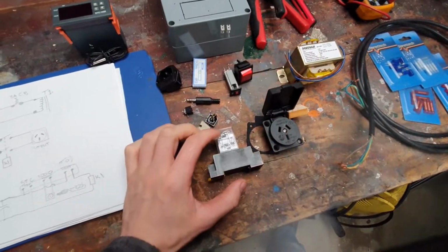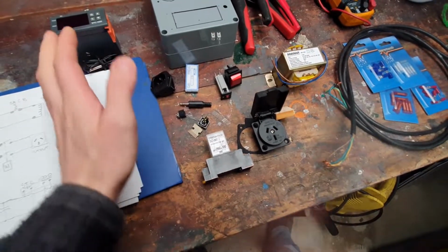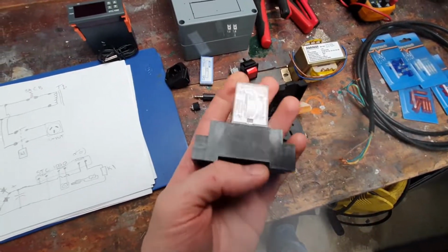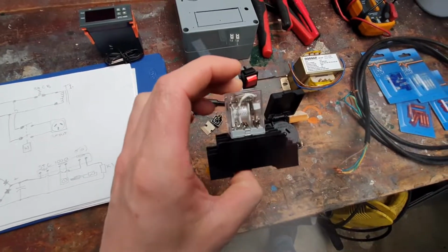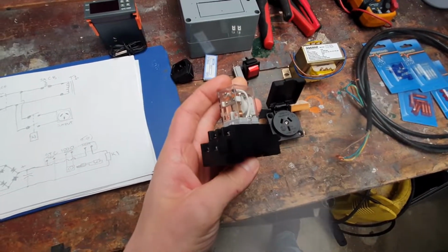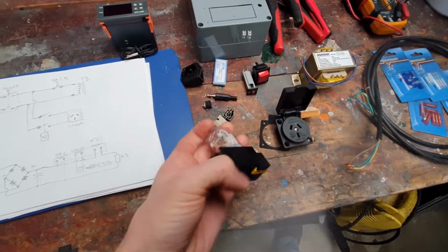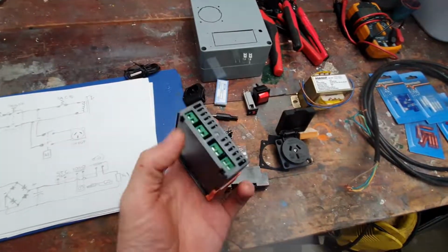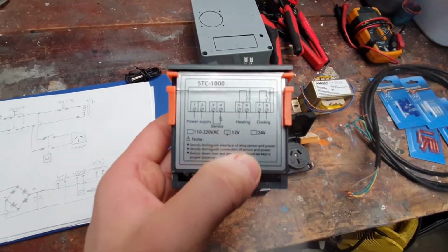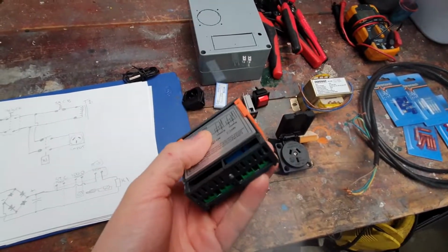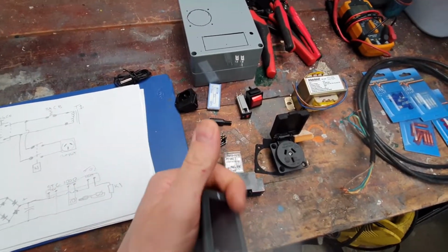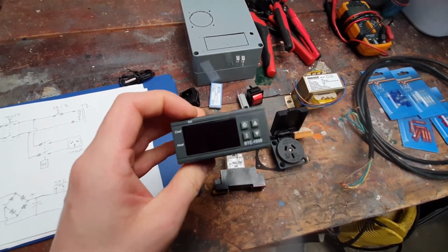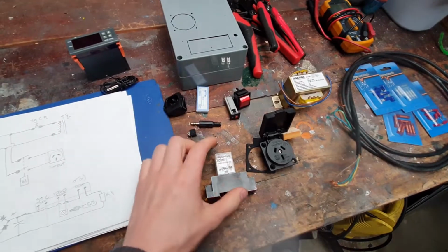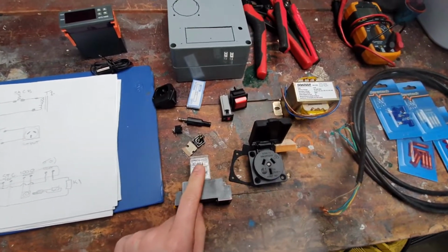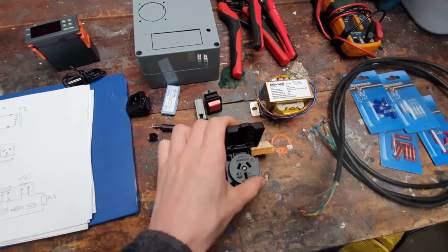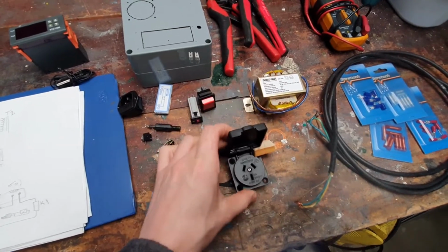Now for the step down transformer, because it's 12 volts, I decided to get a 12 volt relay. This relay will switch the heater. It's a 10 amp relay, double pole, double throw, because the relay built into here, although it says 10 amps, I do not trust it because I've seen what's actually inside, and the relay is like the size of my thumbnail. I wouldn't trust that with 2400 watts, so I'm going to use it to switch this much bigger relay. On the other side of that relay, the power will just go straight to this output socket, so I can plug literally any kind of heater into it.